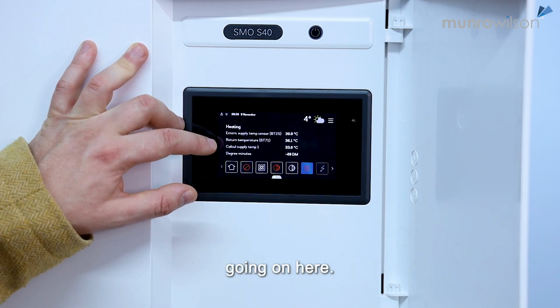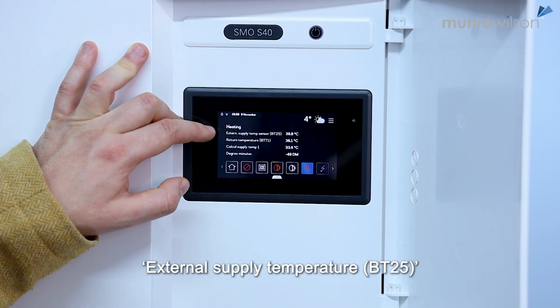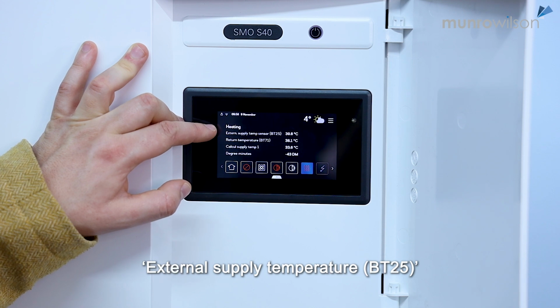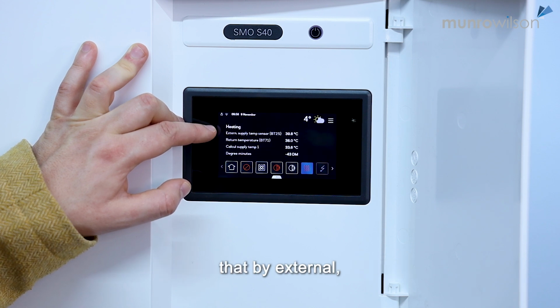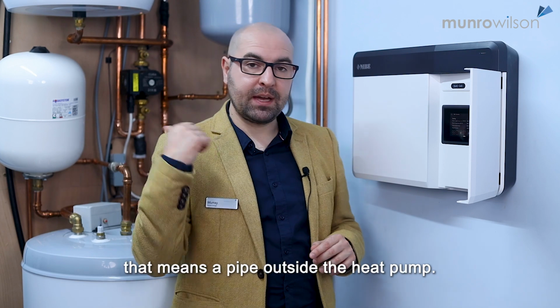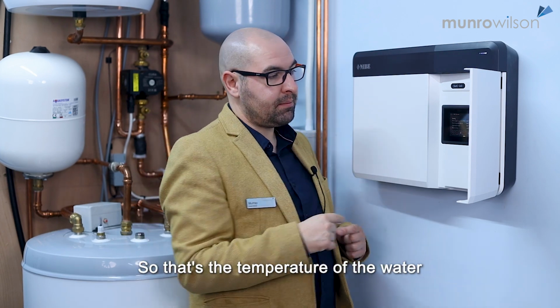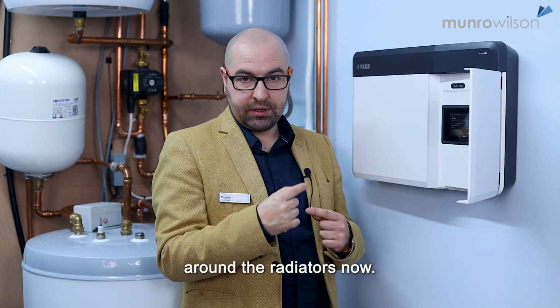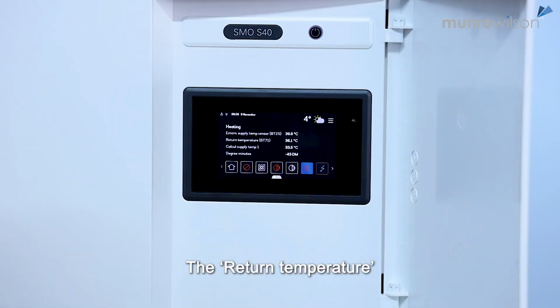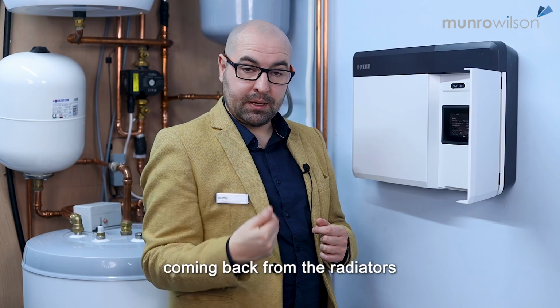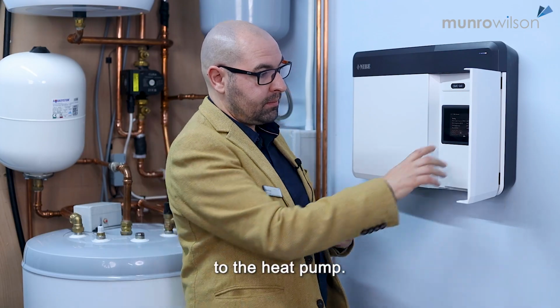and there's a couple of temperatures going on here. So there's the external supply temperature, BT25. By external, that means a pipe outside the heat pump. So that's the temperature of the water that's actually flowing around the radiators now. The return temperature is the temperature of the water coming back from the radiators to the heat pump.